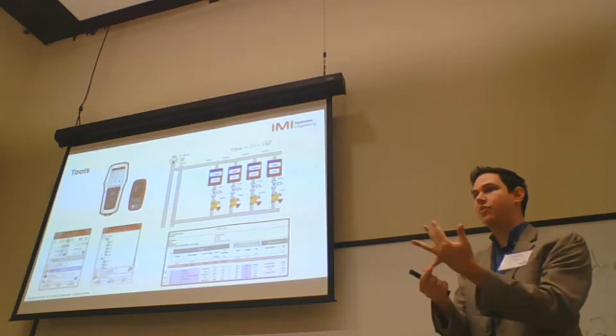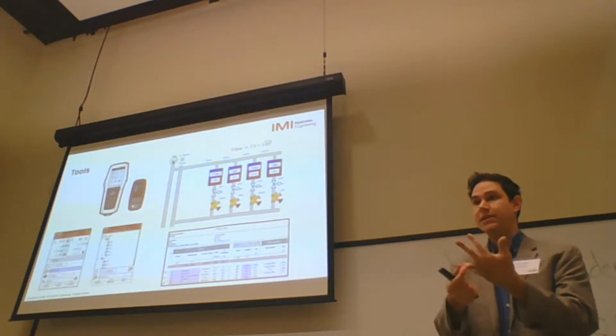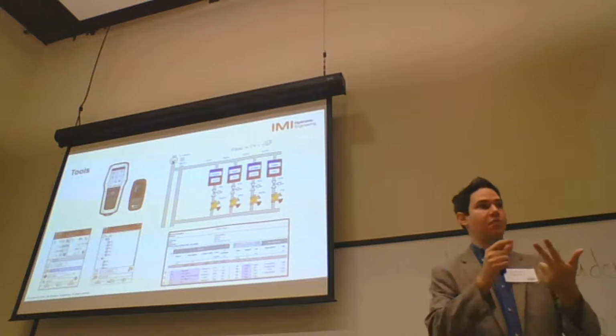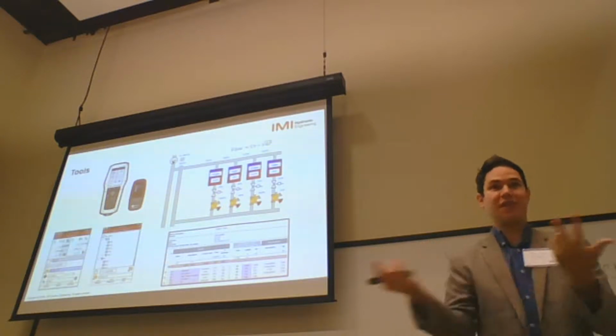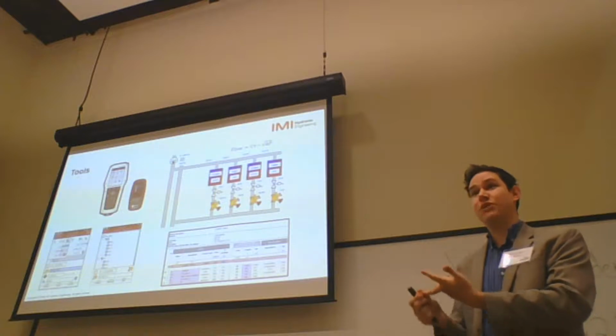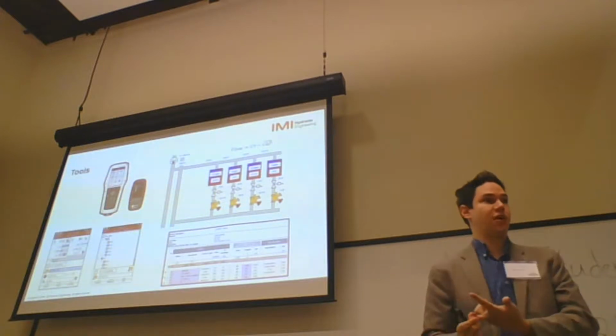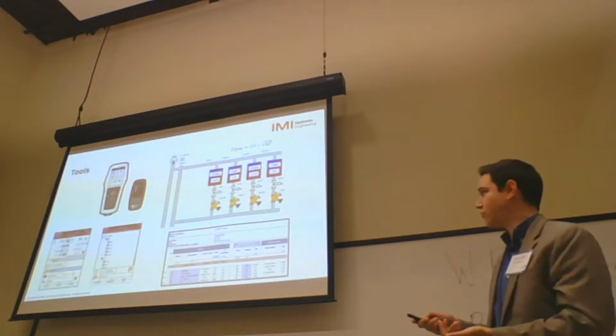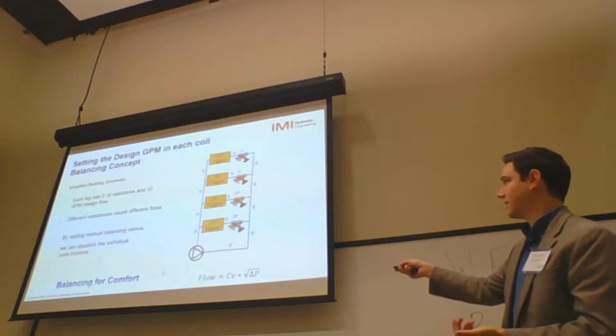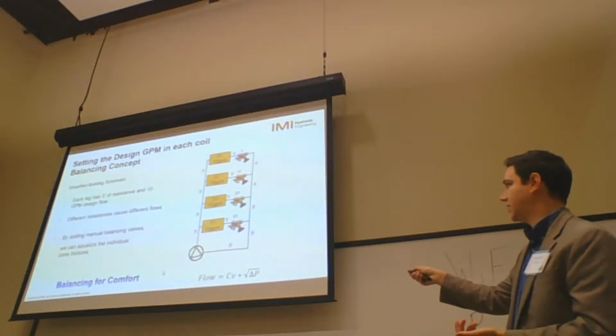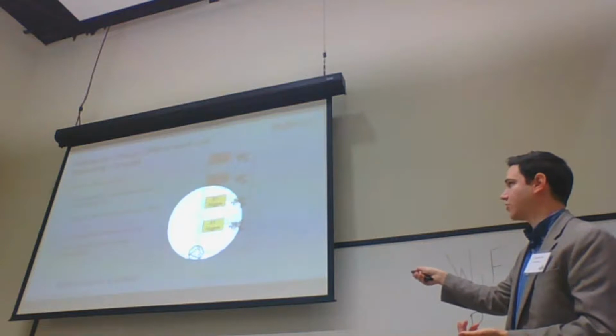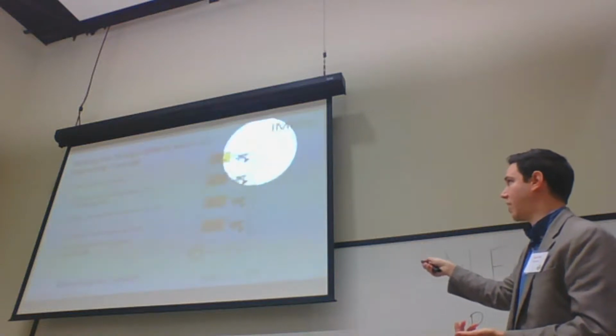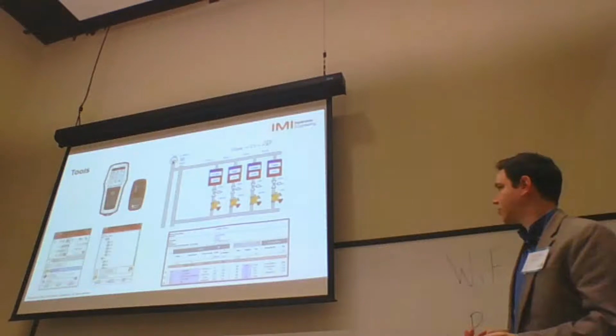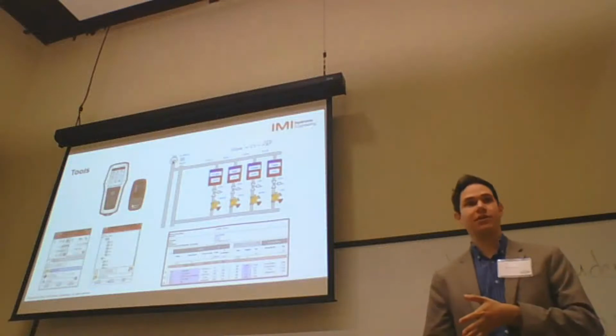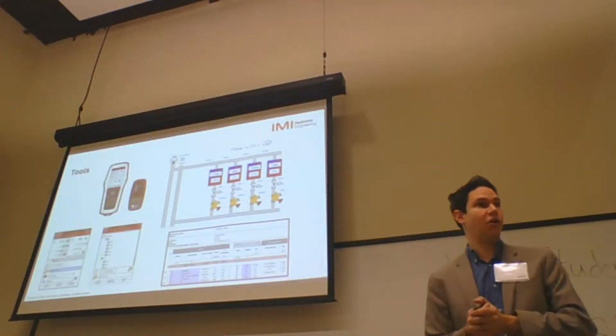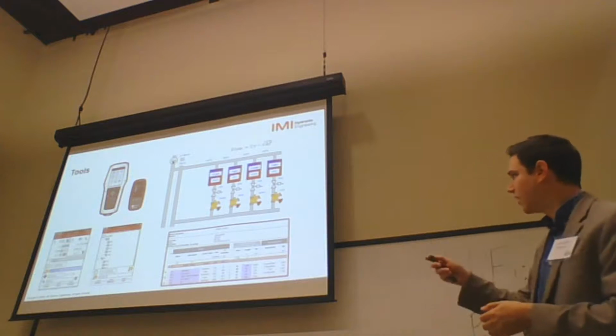It does give you the pump head calculation, where to place a DP sensor to control a variable speed pump, and also, I think the most important here, the presetting for each balancing valve in the job. So basically the software is calculating exactly the same as we see on this slide. The software is calculating the actual pressure drop in each piece of pipe of the whole installation to be able to determine what is the valve position in all of the coils in the installation.